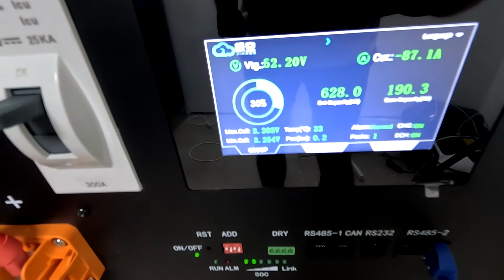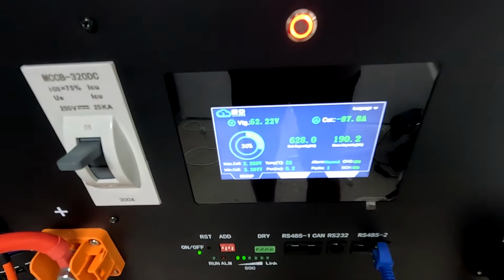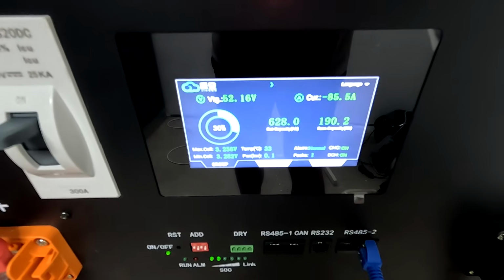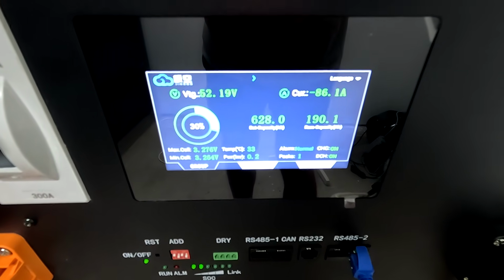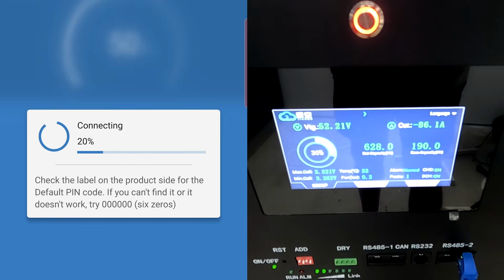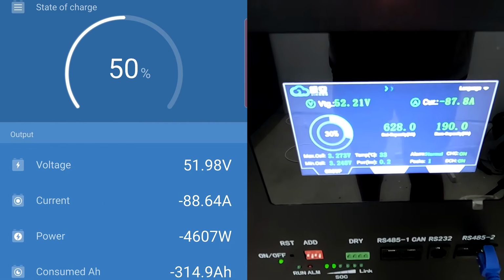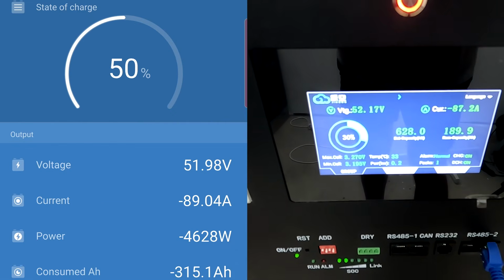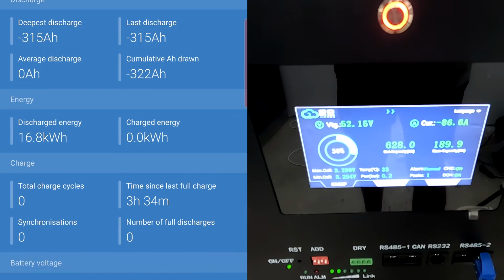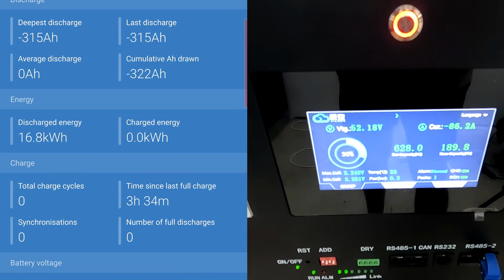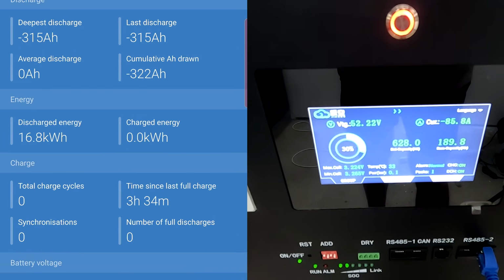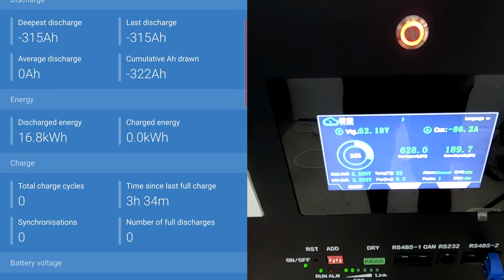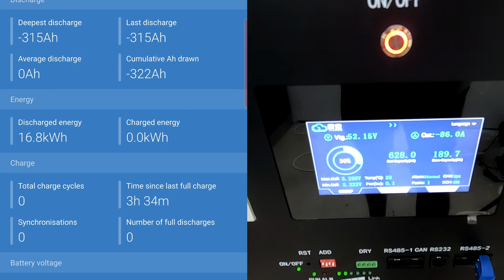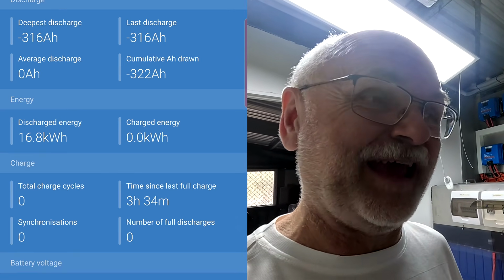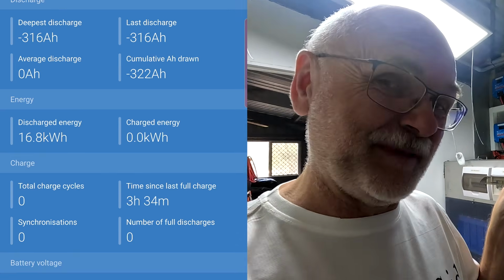Alright, we have now reached 30% state of charge, but this is just what the JK inverter BMS claims. Let's have a look at the SmartShunt, because this one says we are at 50% state of charge. And it makes a lot more sense, because we have discharged now 322 ampere hours times 2 makes 644, and this is for a 628 ampere hour rated battery, so that makes far more sense than the JK inverter BMS.